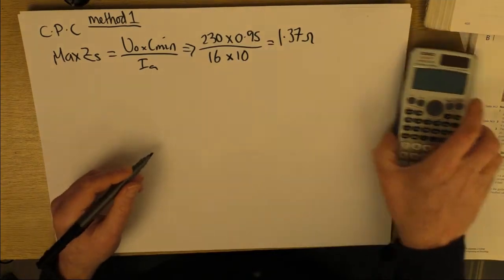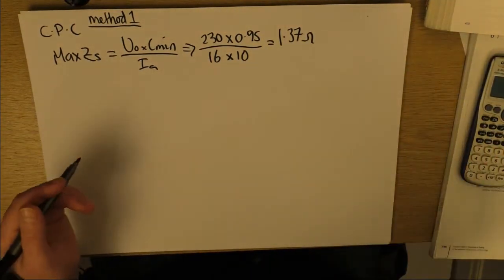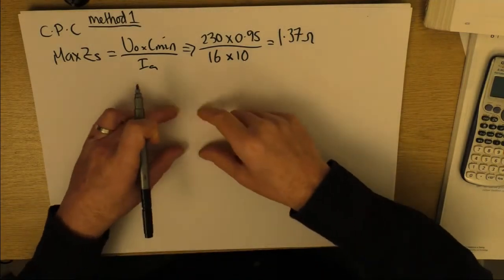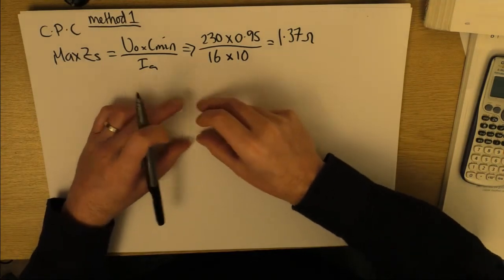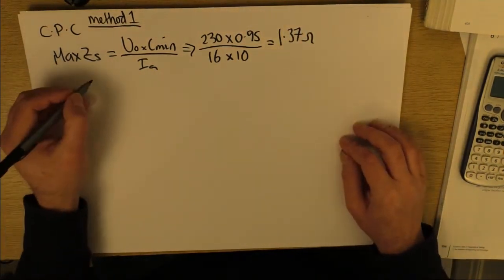Now that's at fault temperature, when it's running, so it'll be at the limiting temperature, 70 degrees. So in a minute, we're going to need to calculate our R1 plus R2, but we need to get our R1 plus R2 up to that temperature, so we've got a fair comparison.